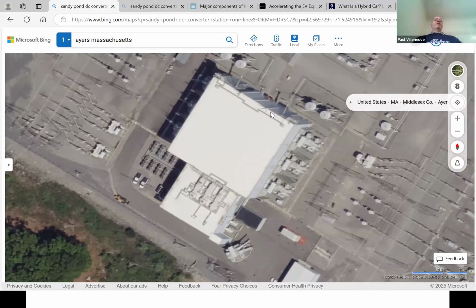The thing about this one is it's plus/minus 450 kV. So it goes plus 450 relative to ground and minus 450 relative to ground. So the actual potential difference between those 2 incoming phases or poles is 900 kV — almost 1,000,000 volts.